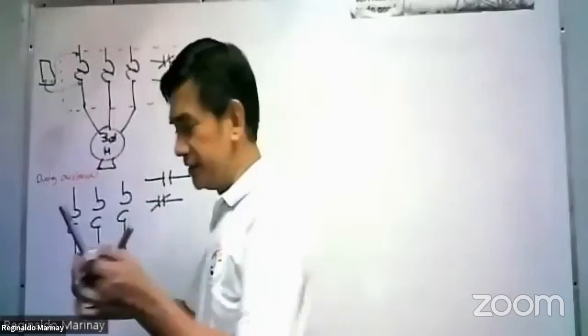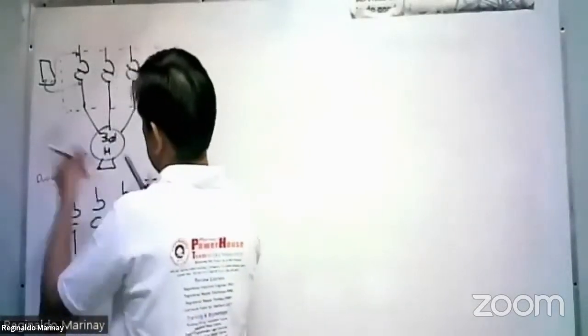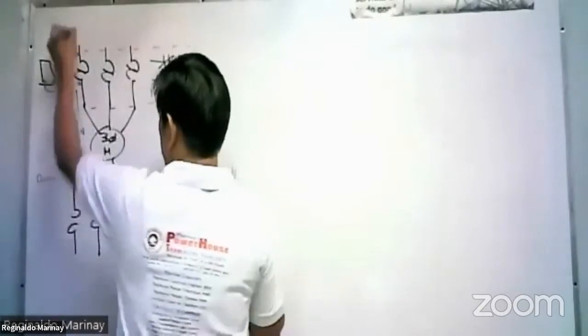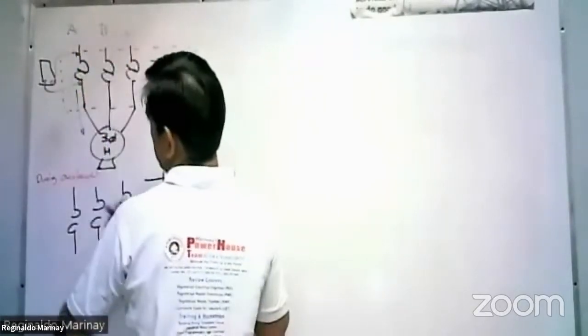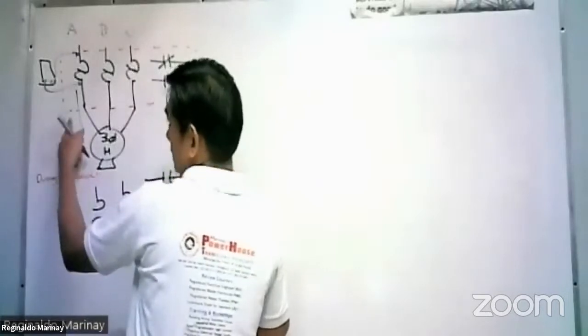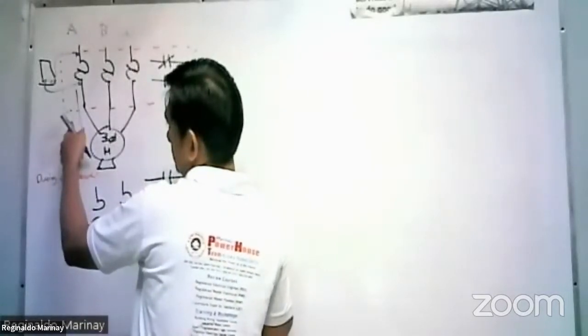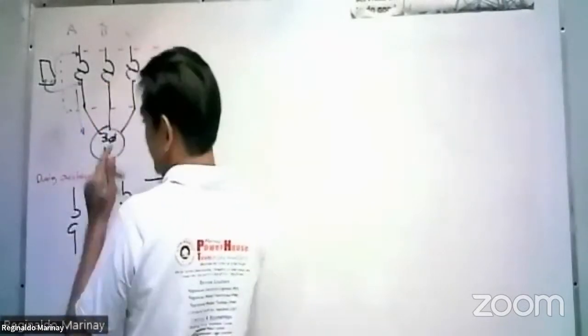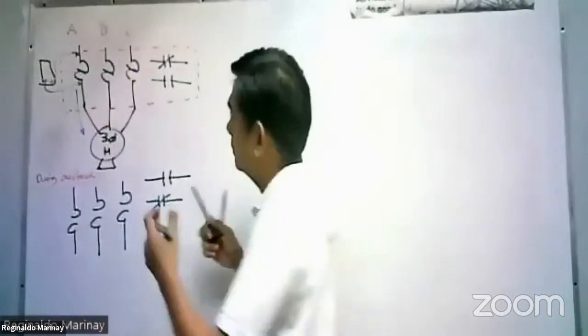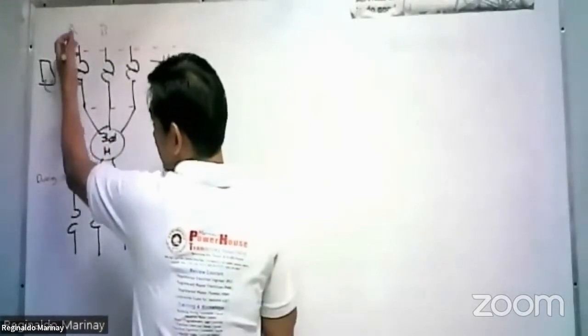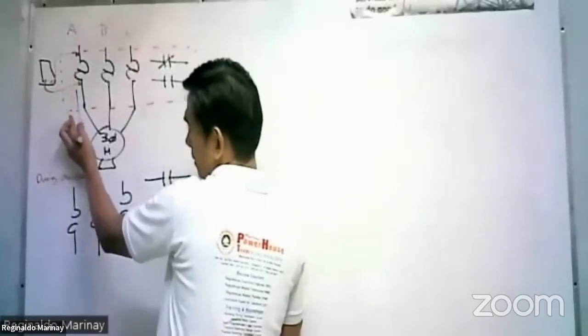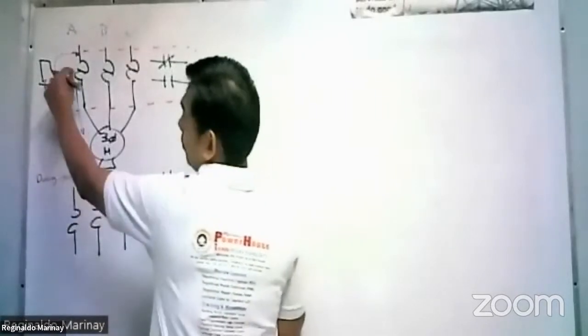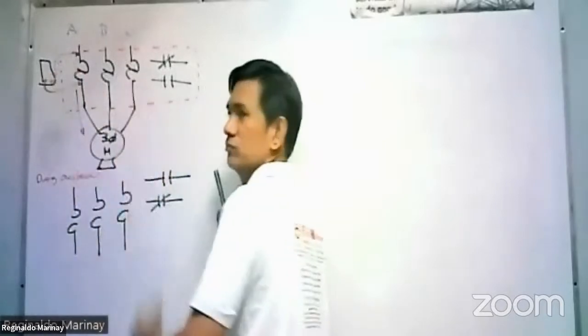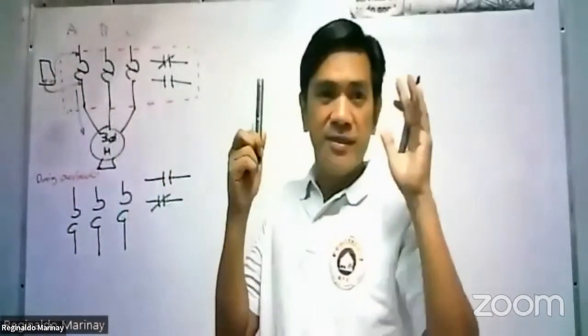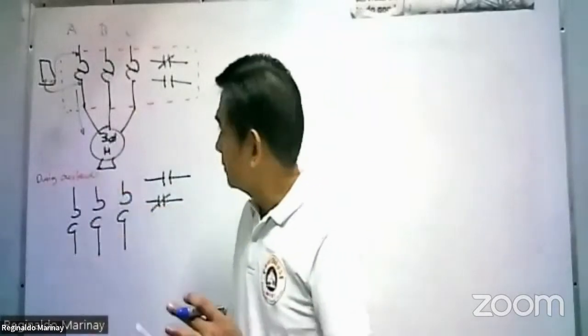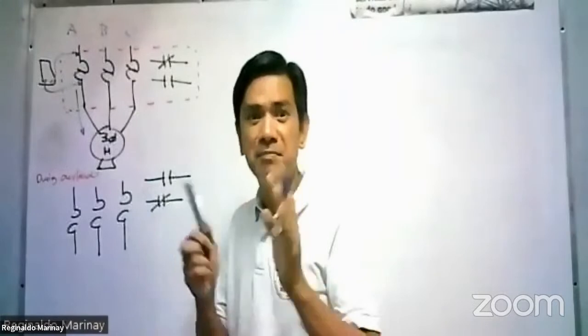Even though the overcurrent is just on line 1 or phase A, let's say phase A, phase B, phase C. Even though the overcurrent is just on phase A, this should also be open. That should also be open. Isn't it said that only phase A is overloaded? So only that one should open. No, that's wrong. That is not the case for the overload relay. It should not be happening.